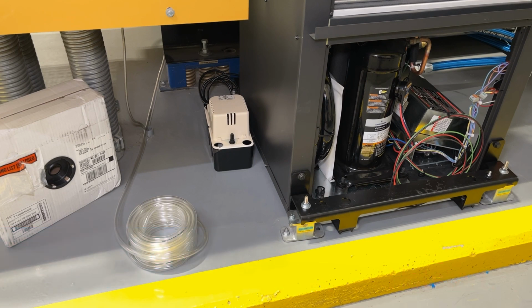During normal operation, the air drawn into the unit is dehumidified, producing condensate on the surface of the evaporator coil. This condensate is collected in the coil drain pan and must be piped away to a suitable drain system. Determine a suitable location for condensate drainage within the room. If needed, a condensate pump can be used to transfer condensate to a location away from the heater. Position the condensate pump near the heater on a flat level surface.